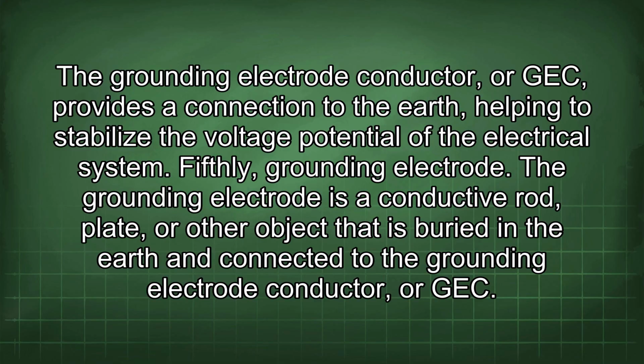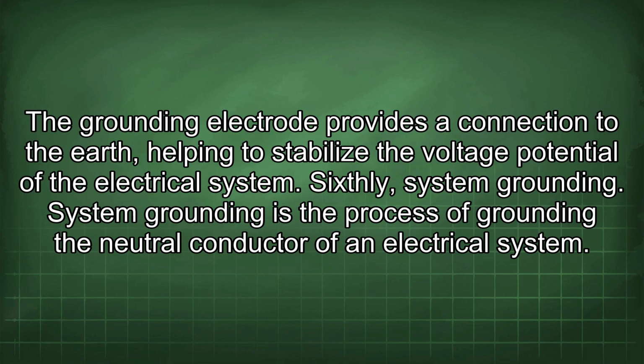Fifthly, grounding electrode. The grounding electrode is a conductive rod, plate, or other object that is buried in the earth and connected to the grounding electrode conductor, or GEC. The grounding electrode provides a connection to the earth, helping to stabilize the voltage potential of the electrical system. Sixthly, system grounding. System grounding is the process of grounding the neutral conductor of an electrical system.